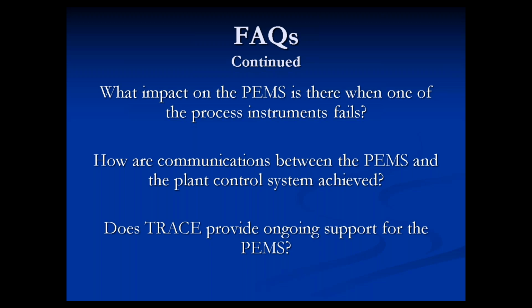The other question we've gotten is, how do we achieve communication between the PEMS and the plant control system? As alluded to earlier, it's most typically done via an open protocol such as OPC or Modbus, and that's down to the detailed engineering that Dave alluded to earlier. That is part of our project scope. Our lead engineer on the project will get with your instrument engineers and will determine what the best means is for that bidirectional communication to be achieved.